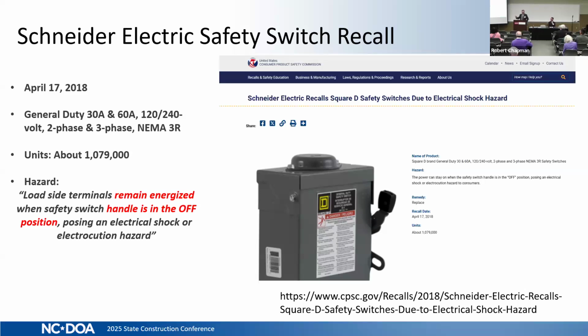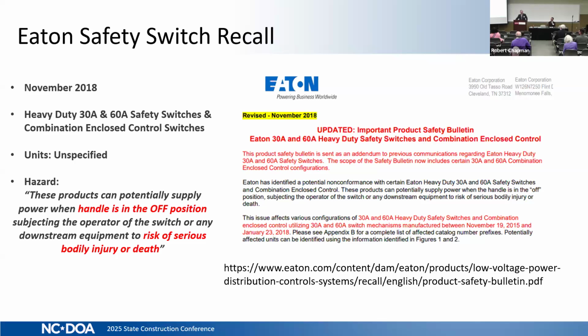In 2018, Schneider Electric, which a lot of people know as Square D, had to issue a recall for over 1 million of their safety switches because when you turned the switch off, it was still allowing the load to be energized. The same thing happened the same year with Eaton Cutler Hammer. I can't find the basis for this, but my conclusion, because of the commonality of the year 2018, is that more likely the original equipment manufacturer, the OEM that supplied the switches to Schneider Electric and Eaton, is the entity at fault, whose switches still didn't work when they turned the switch off. So anyway, those are illustrations of why we have this new requirement from OSHA.